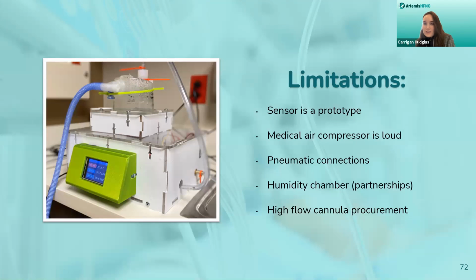Yeah, so I see that we've navigated to the limitations slide here. You also asked about that, and I can speak a bit to the current limitations. There are some inherent flaws with the device, given that it's currently in a prototyping stage. The combined flow and oxygen sensor that we've been using is a prototype that we acquired from an external company. It has a bit of a delay sometimes, which can contribute to delays with our FiO2 oxygen concentration readings. So we would need to get a more high fidelity sensor there.